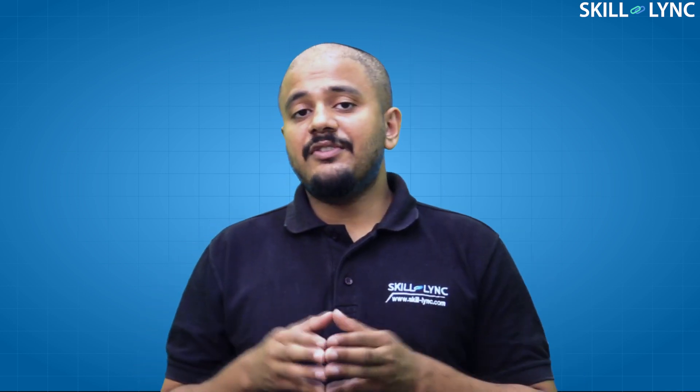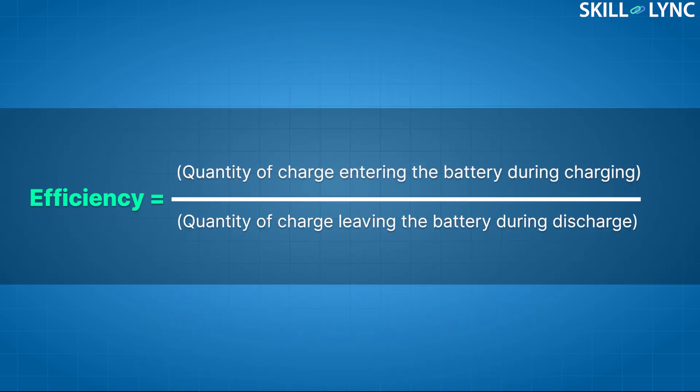The efficiency of a battery also plays an important role in its usage. Battery efficiency is a ratio of the amount of charge entering the battery during the charging phase to the amount of charge leaving during the discharge phase. This value is dependent on the rate of discharge — if the battery is discharged at a much faster rate, the efficiency reduces. Lithium-ion batteries tend to have very high efficiency of 92 percent against 60 percent efficiency of lead-acid batteries for similar capacity and discharge conditions.